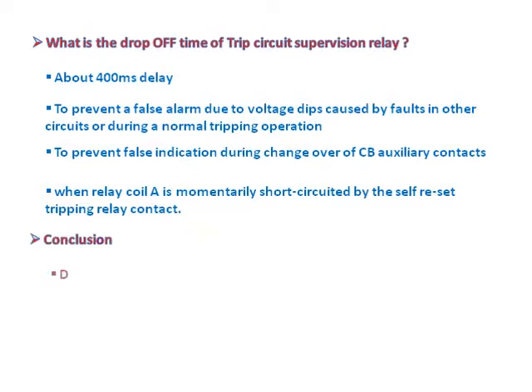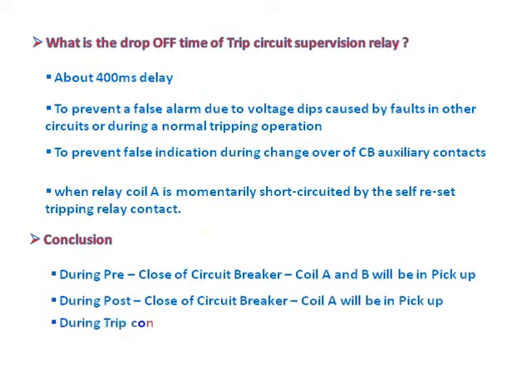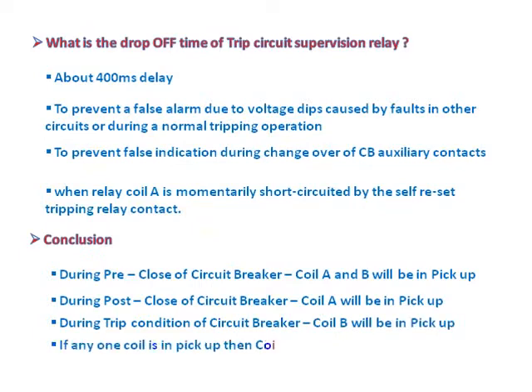Conclusion: During pre-close of the circuit breaker, coil A and B will be in pick up. During post-close of the circuit breaker, coil A will be in pick up. During trip condition of the circuit breaker, coil B will be in pick up. If any one coil is in pick up, then coil C will also pick up, as discussed earlier.